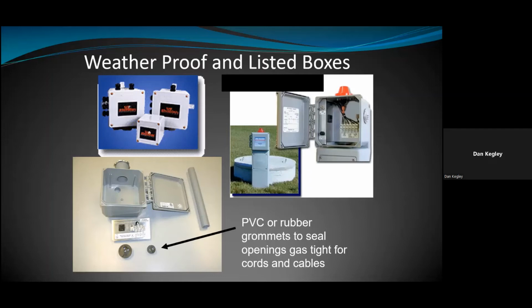Definitely. And then there's another one here. It says, with the direct burial of the UF cable, is it a requirement to put some type of marker, like marking tape, a certain number of inches above the cable, indicating that a cable is buried below? The state of Wisconsin does not have that requirement, nor does the National Electrical Code. There is a reference to marking tape for service conductors, where you have the service conductors coming in to feed a meter on your house and those kinds of things. But for branch circuits going out to pumps and light fixtures and those kinds of things, there's no requirement for any kind of marking tape. All right. And is it a good idea? Yeah, it's a good idea.